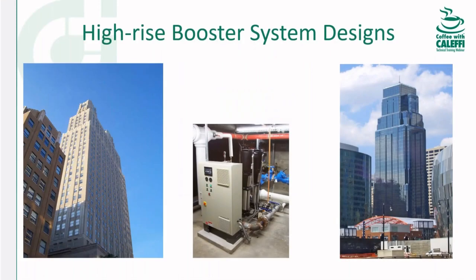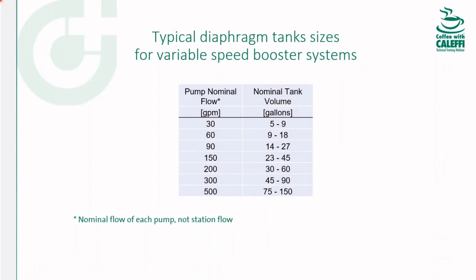And okay. As you can see, they're not very big either. So we see specifications all the time now for a booster that has, for example, 100 GPM pumps, maybe two or three, and they'll specify a 200 gallon tank. But really, if you have a pump that does 100 gallons a minute, you only need a tank in the range of maybe 20 to 30 gallons or so.